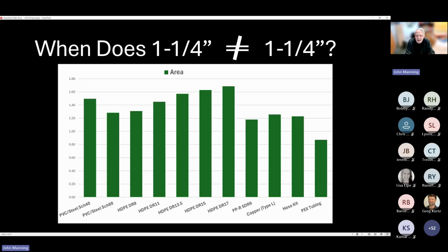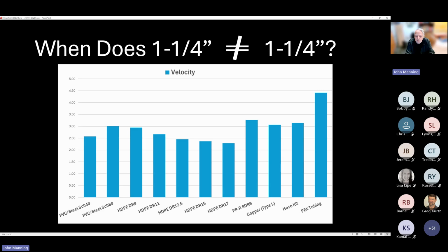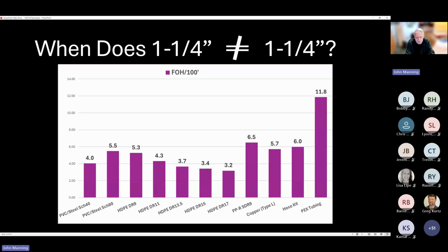No, it's really area. So when we square that radius, the deviation in area starts to really stand out. And that area translates to a fluid velocity. So at 12 gallons a minute, each one of these pipe materials, even though they're all 1 1/4 inch, are operating at significantly different velocities. Now, it's not velocity that's important, it's the square of velocity that dictates pressure drop. So even though all these pipe materials are 1 1/4 inch, the pressure drop per 100 feet of pipe ranges from 3.2 feet of head to 11.8 feet of head.